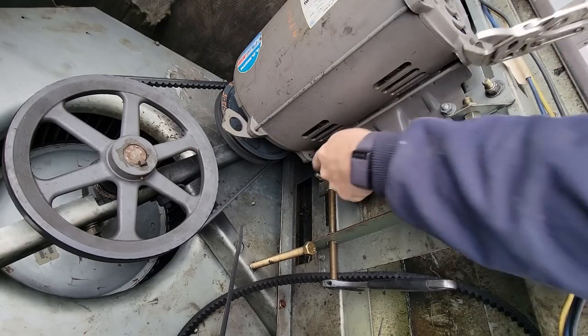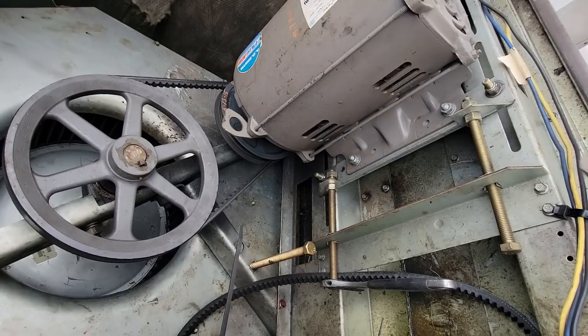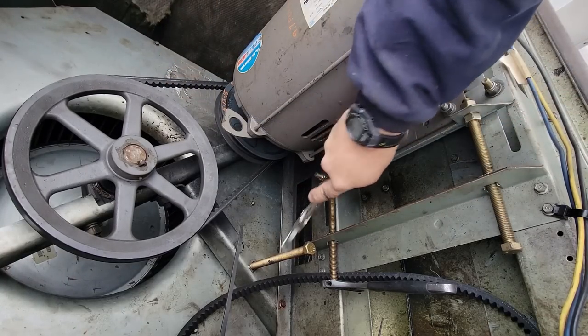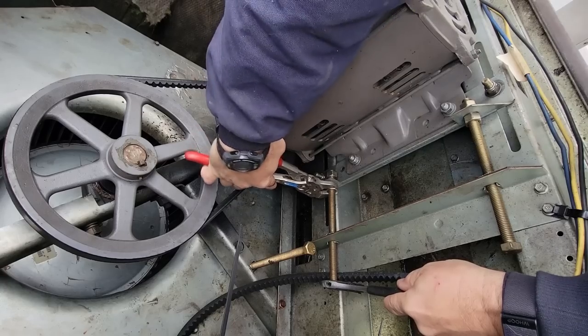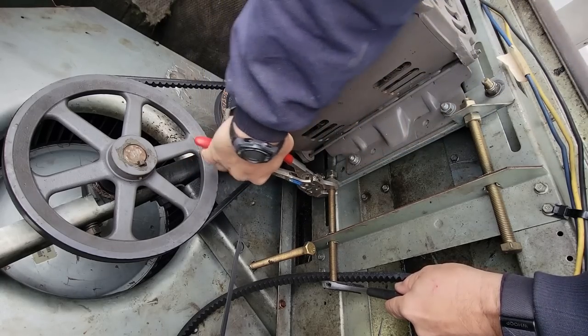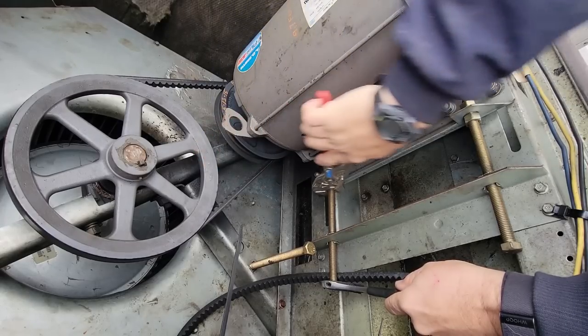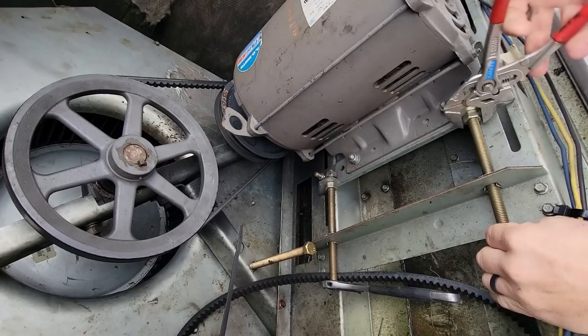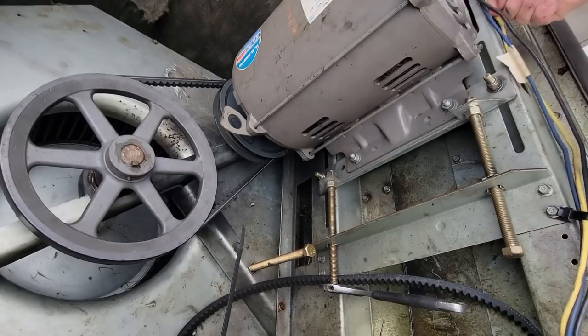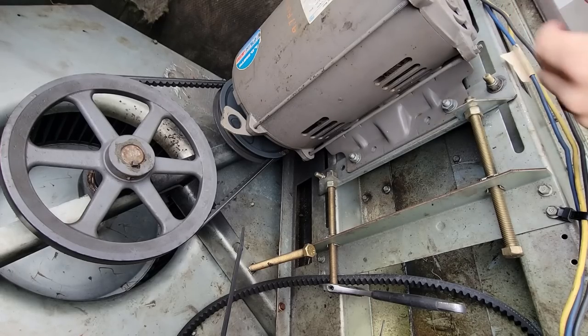I did have to loosen up the four corner bolts — still hasn't moved much. This thing is nothing but a grease hole; the building's got oil floating in it and it gets all over everything. Getting better, not there yet. Got that tightened up quite a bit. The new pulley I replaced seven years ago is worn a little bit.